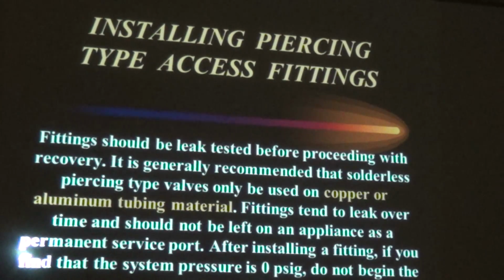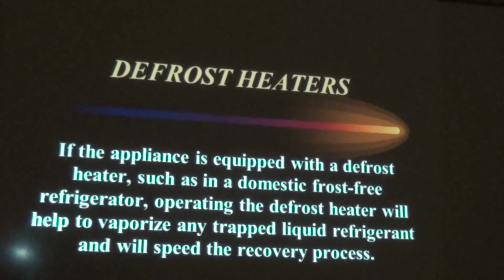So once you recover the refrigerant, you're going to take these valves off. They're going to leave two holes in the suction line and a hole in the liquid line. You're going to split the pipe, and you're going to put a Schrader in there in its place. If you're lucky enough to have a defrost heater around the belly of your compressor, such as in a domestic frost-free refrigerator, turn on the defrost heater to help vaporize any trapped liquid refrigerant, and that will help speed the recovery process.